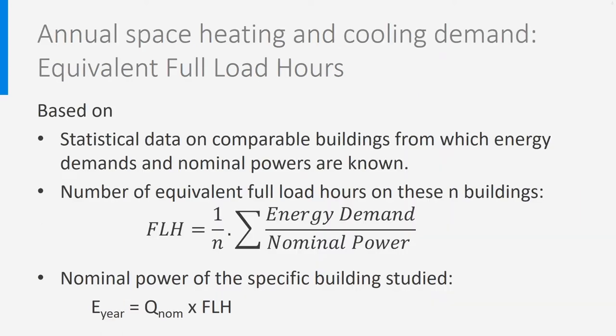The first method is to use equivalent full load hours. These equivalent full load hours are determined by studying the ratio of energy demand and nominal power for a large number of existing buildings. The average ratio of both is what we call the equivalent full load hours. Once you know these full load hours for your region and for the types of buildings under consideration, you just need to multiply the nominal power of your specific building by the full load hours to get an estimate of its yearly energy demand.